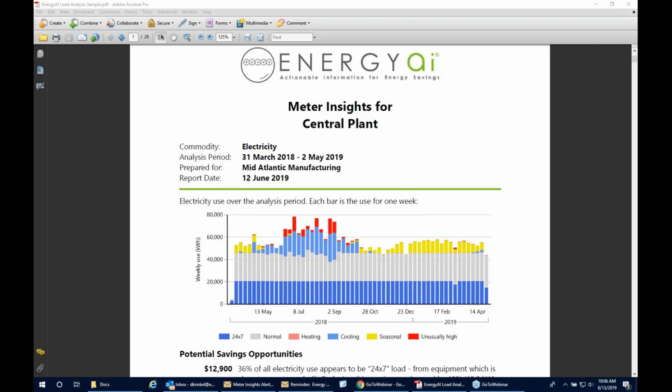We said, let's look at the recent week of data. I think they had hourly data we were able to collect at that time. We had on screen in this auditorium the most recent week of data, and we thought, geez, isn't this great? You can see rising and falling and whatnot. And from the back of the room, one of their folks, who in fact was an IT person, not even a facility manager or an energy person, said, hey, something's wrong. We looked at the data, so what do you mean? And this person said, we're closed on the weekends, this facility. Why is that happening? And she was pointing to Sunday and a bump that was happening on Sunday. And there went our training session.